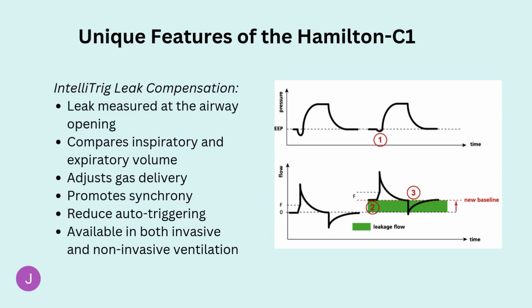Another unique feature of the Hamilton C1 is the IntelliTrig leak compensation. Leak is measured at the airway opening by comparing inspiratory and expiratory volume. The data obtained here will be used to automatically adjust gas delivery to promote synchronization with the baby's breathing and reduce auto-triggering. This feature is available in both the invasive and non-invasive modes.